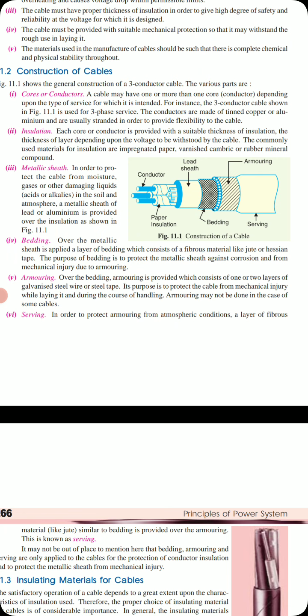You can see here, starting from the conductor core. Conductor core is insulated with the paper. That insulated conductor is given strength with the metallic sheath. Metallic sheath is protected using the bedding. Bedding is once again covered by armoring, where this armoring gives the mechanical strength, and armoring is covered by the serving. So this is the construction of the cable.